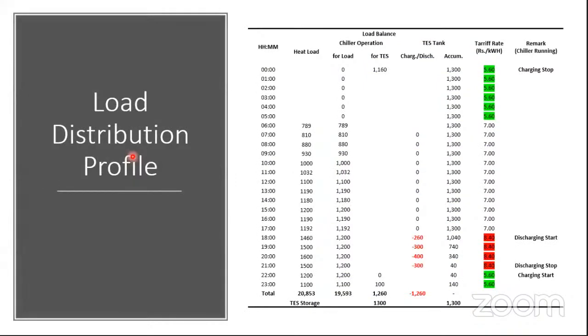So we start with a load distribution profile. When we have an hourly load profile, we start with the load distribution profile and try to figure out what the optimum chiller capacity is that I should design for, and how much load I should keep on thermal energy storage, because it is to be seen whether I have sufficient charging hours for charging the thermal storage.